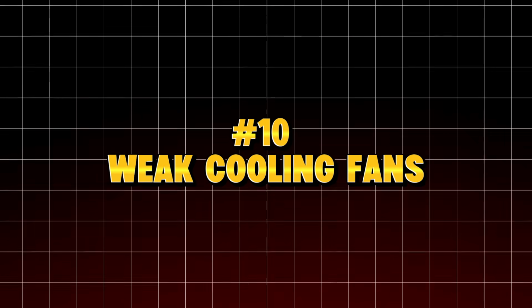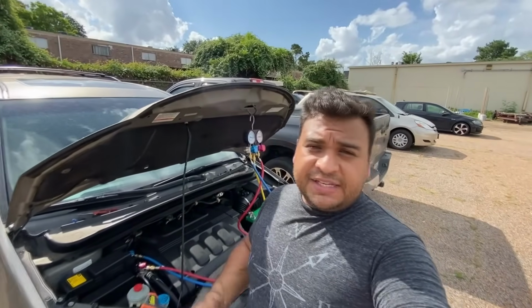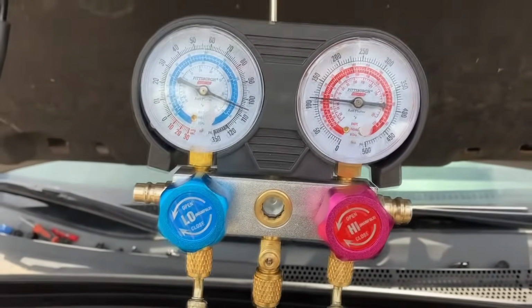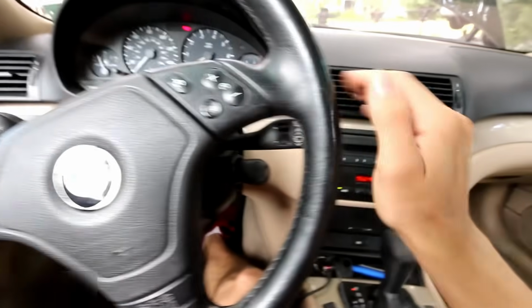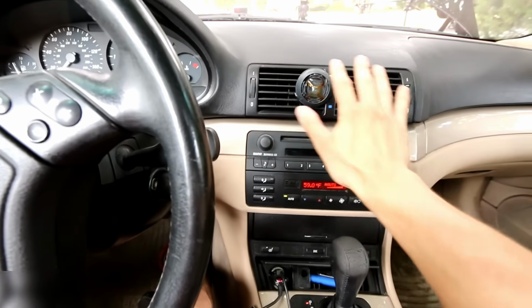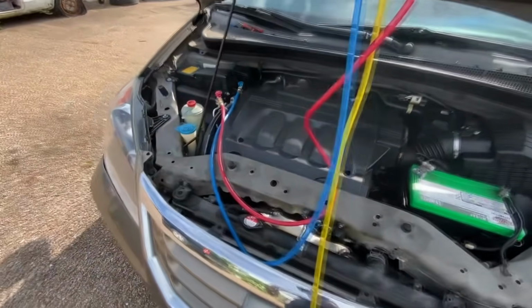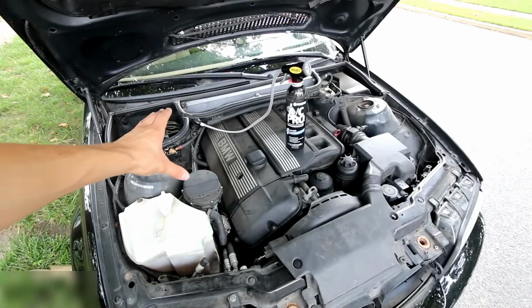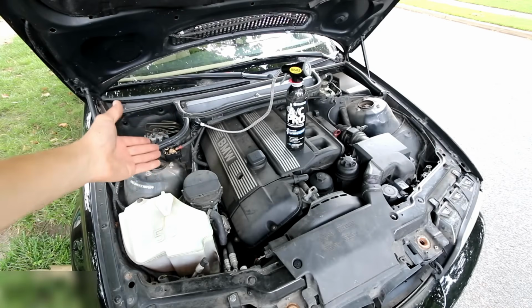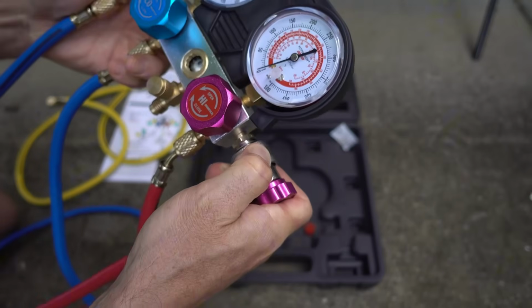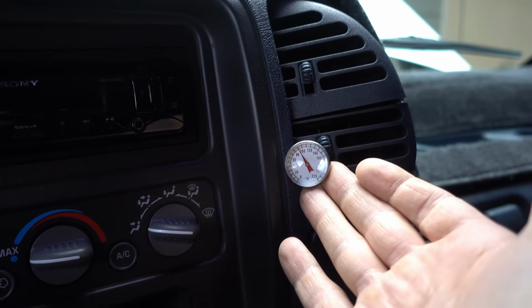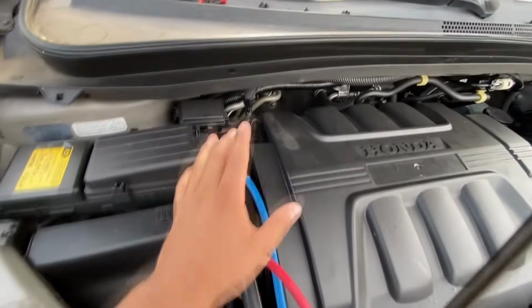Number 9, low refrigerant charge. Yes, low refrigerant is a common cause of weak cooling, but refrigerant doesn't wear out or get consumed. If the level is low, the system almost always has a leak. As refrigerant pressure drops, the evaporator absorbs less heat and cooling performance declines. I've seen many owners recharge their systems every summer. The AC works for a while, then becomes warm again. The leak was never repaired.